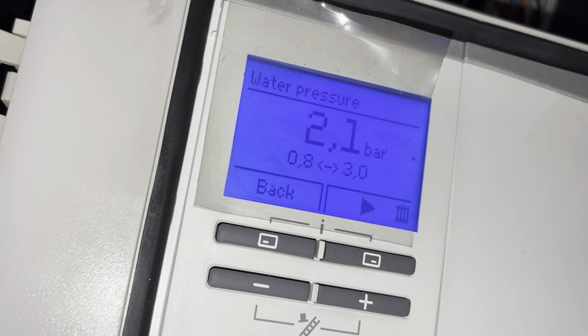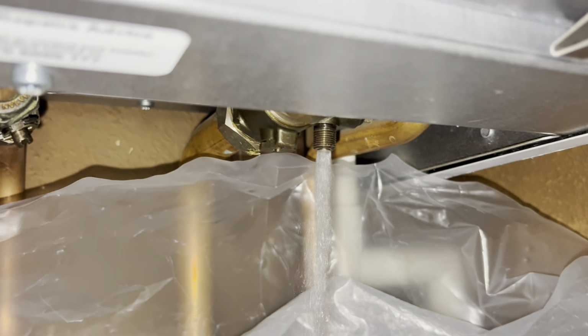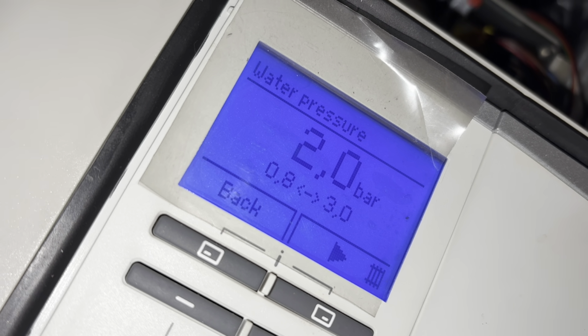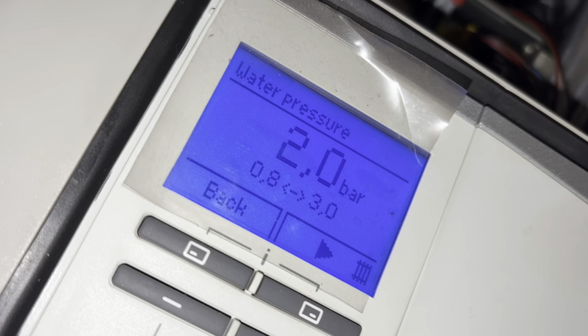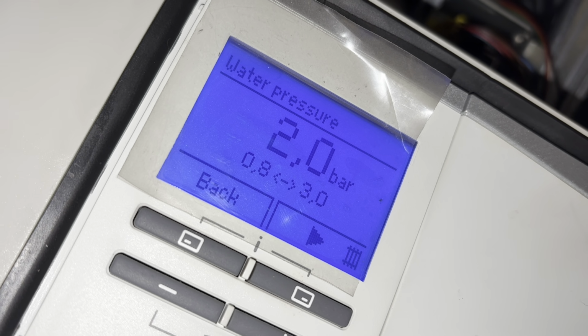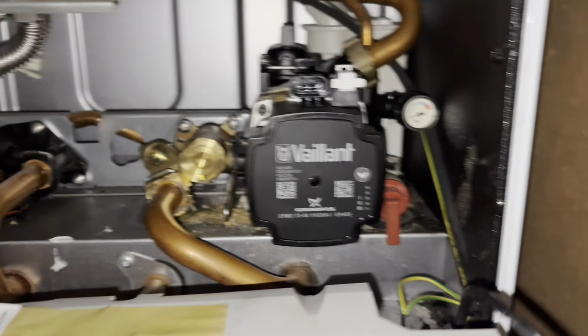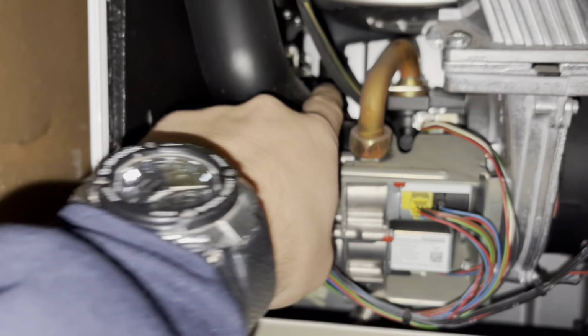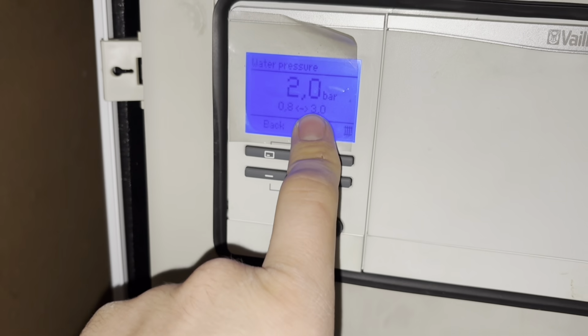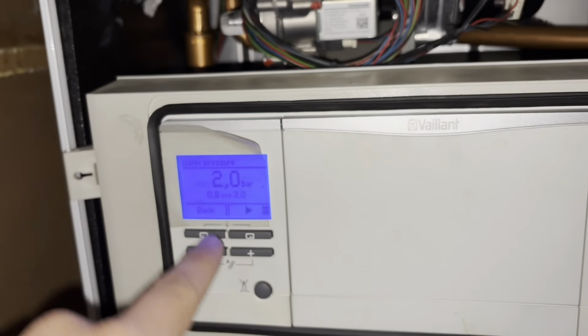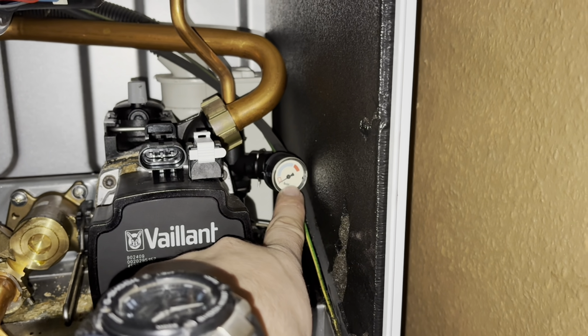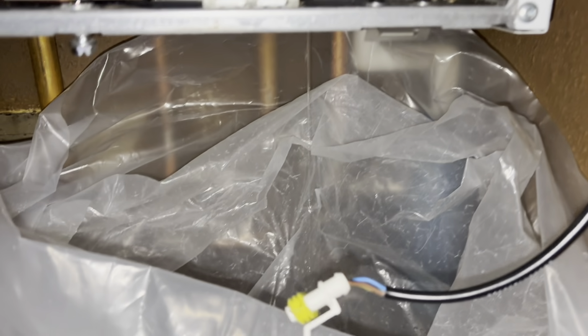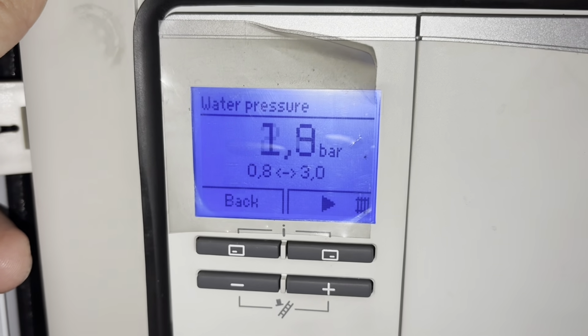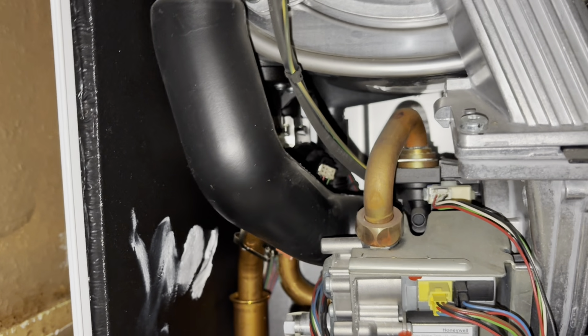Drain on the boiler. Quite a lot of pressure in there. Let that drain down. Might take some time. So sometimes the water pressure sensor is faulty, so when the boiler's drained down and this is still saying 2 bar, that's not good. Gonna have to replace that as well, because it looks like the boiler's nearly at 0. As you can see, the water's stopping now. Well, the boiler still says 1.9, so we will also be replacing the water pressure sensor.